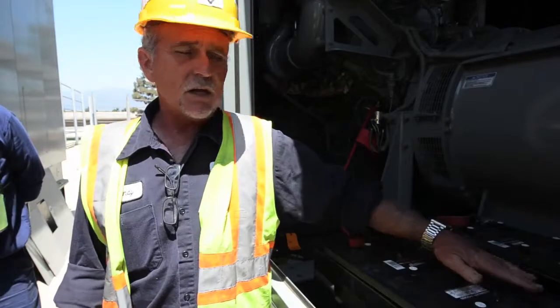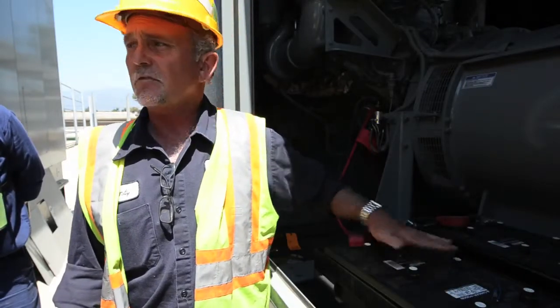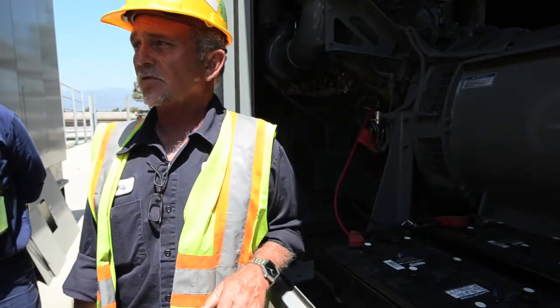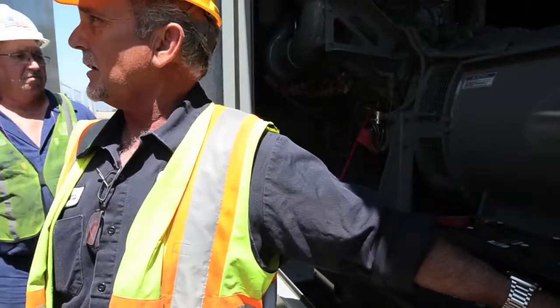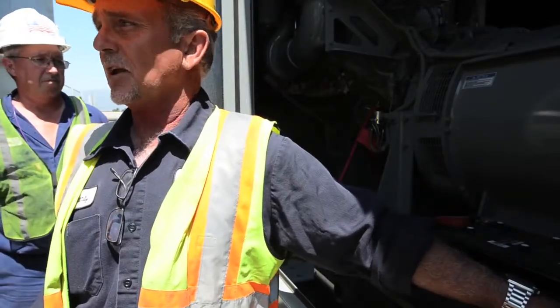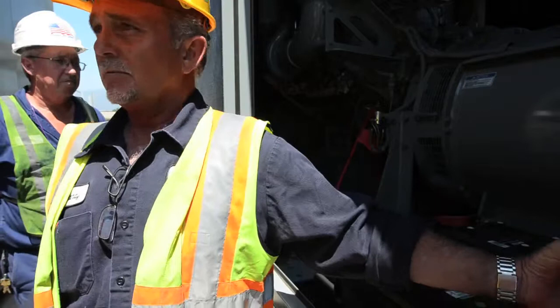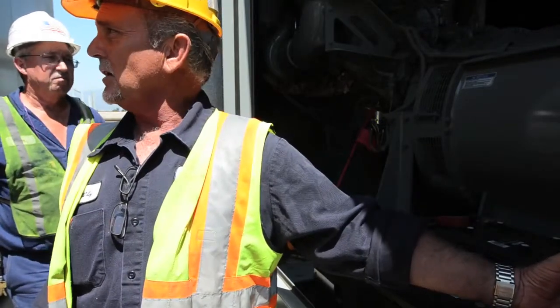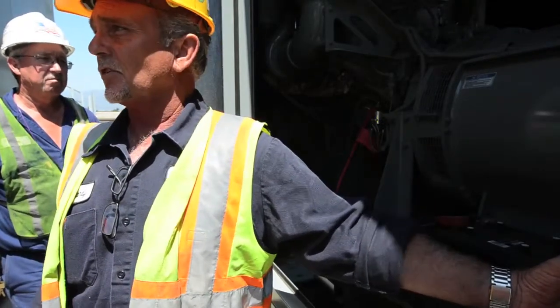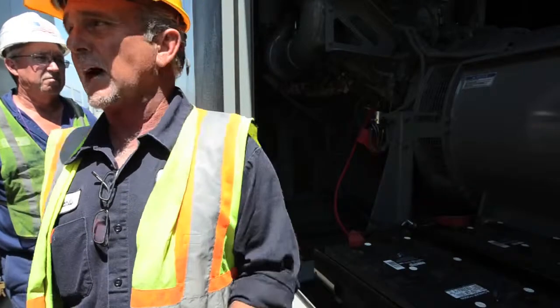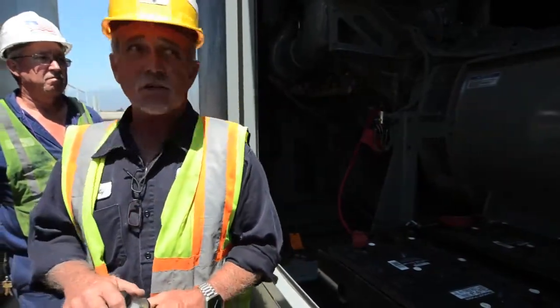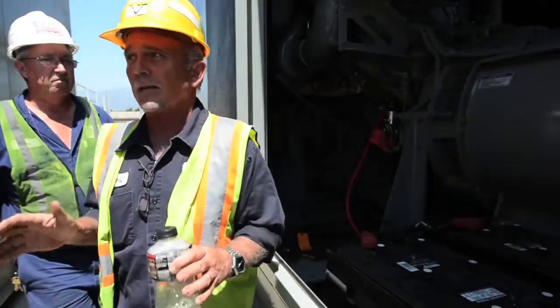These batteries, each set of cells is individually vented. On a maintenance-free battery, you've got one little vent on the end right here. So what you have is an accumulation of gases at this end of the battery. So if there's a spark or an arc or anything else goes bad, we find maintenance-free batteries blown all over the inside of generators.